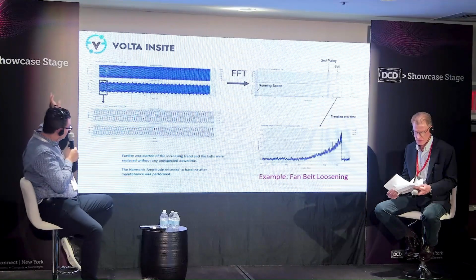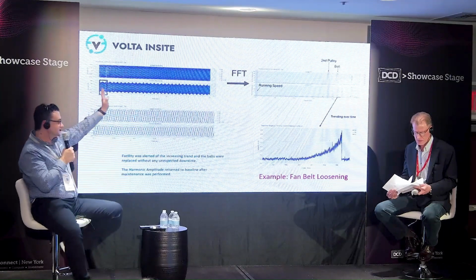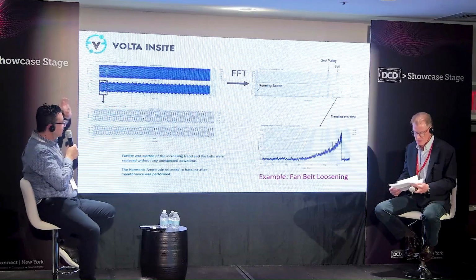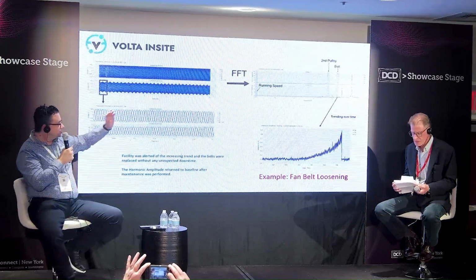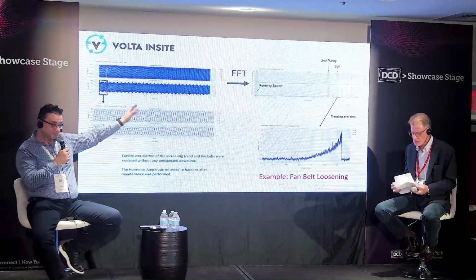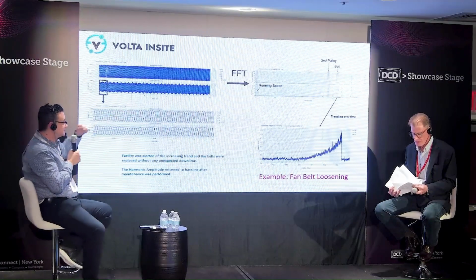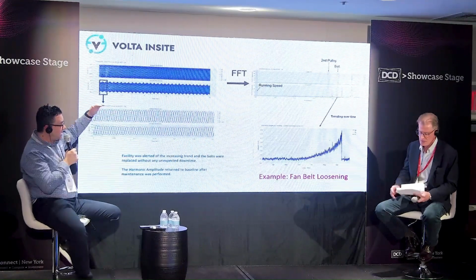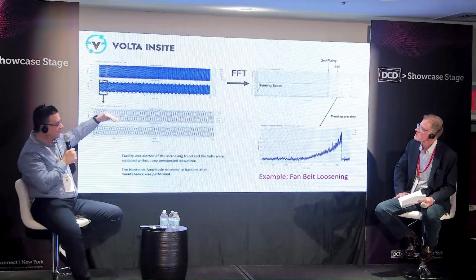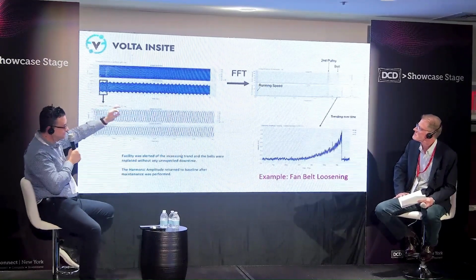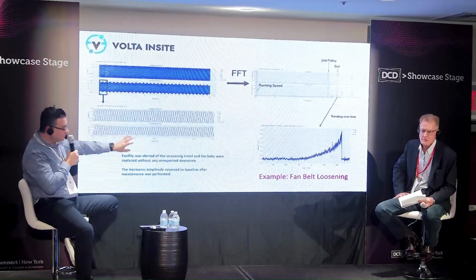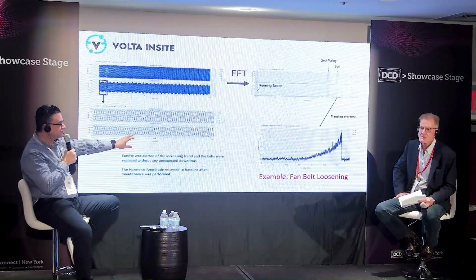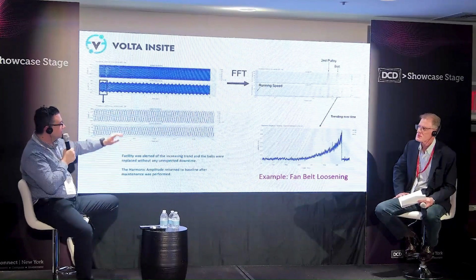So you take your long, let's say 40-second current waveform capture, and you turn that into the harmonic spectrum, so you get a high resolution harmonic spectrum. And as you do that over and over again, you can go and trend specific harmonics over time to see the degradation of that mechanical assembly.